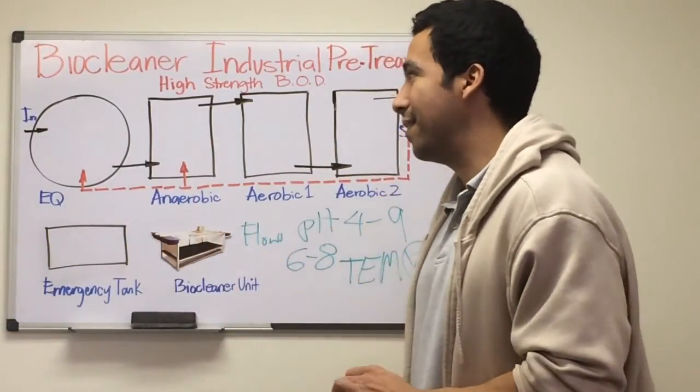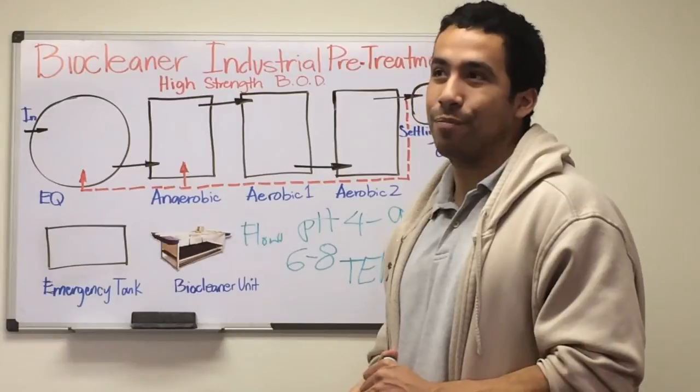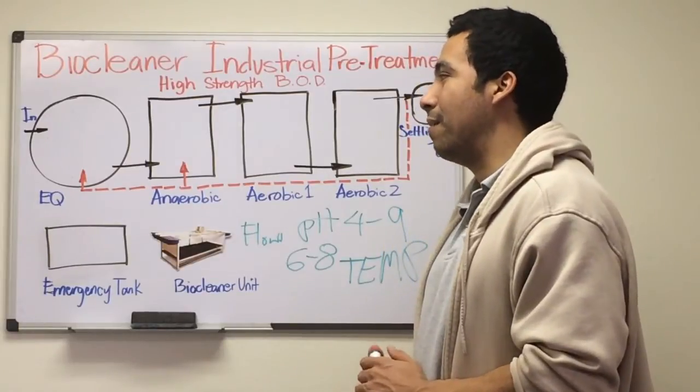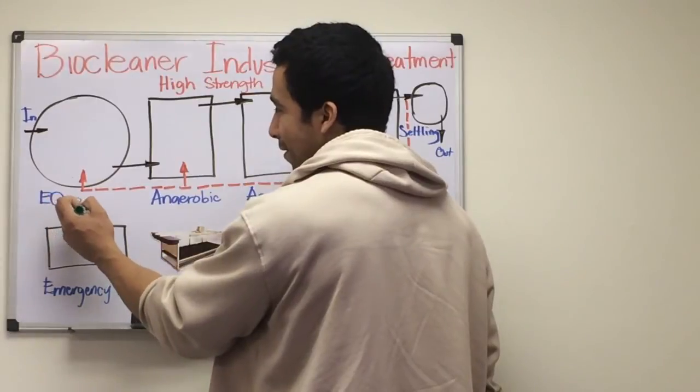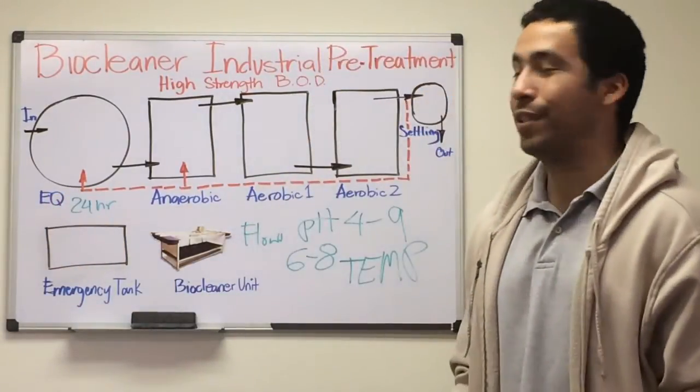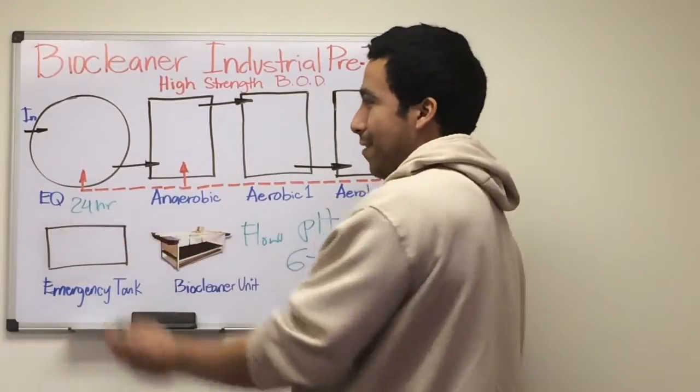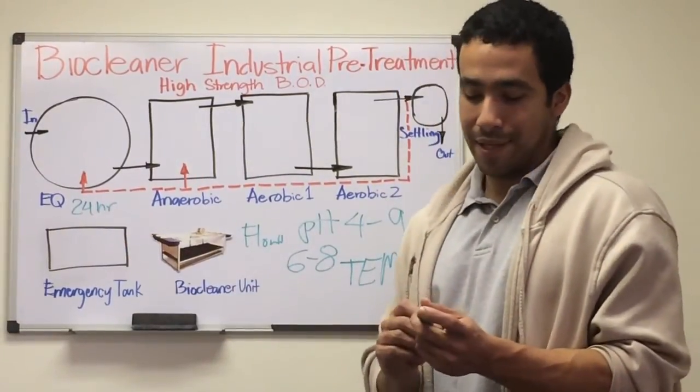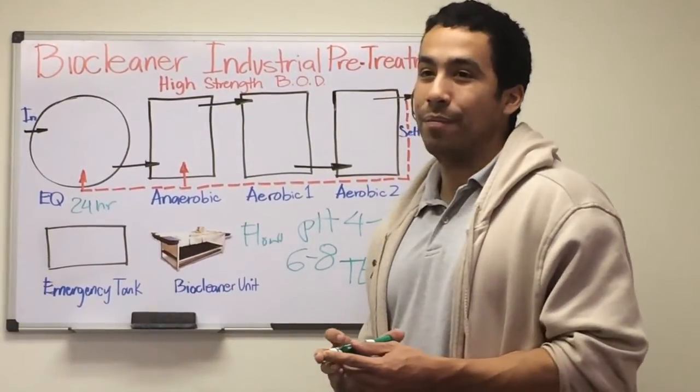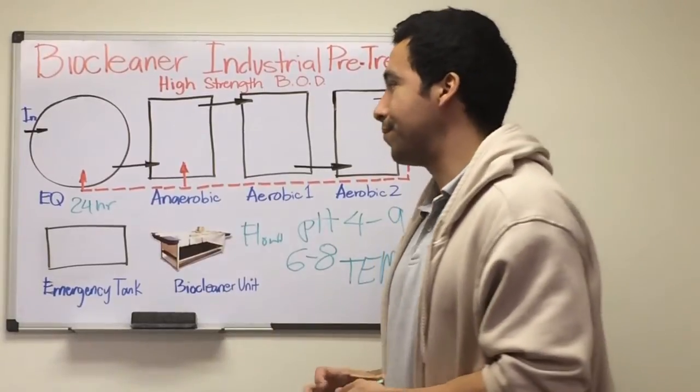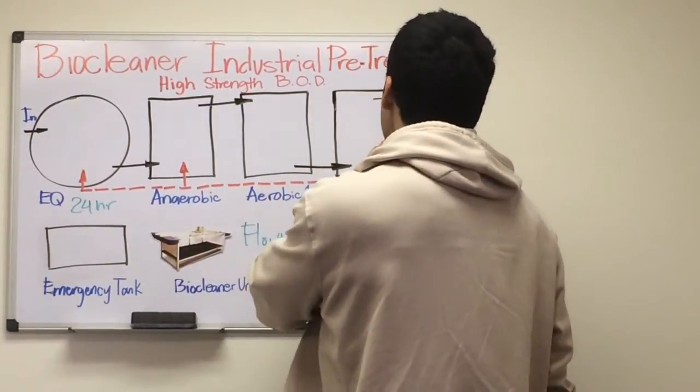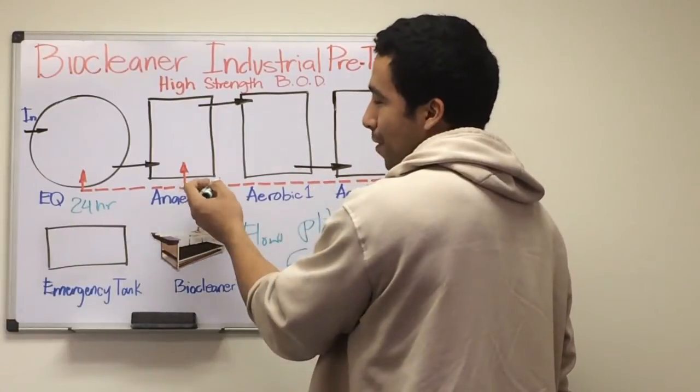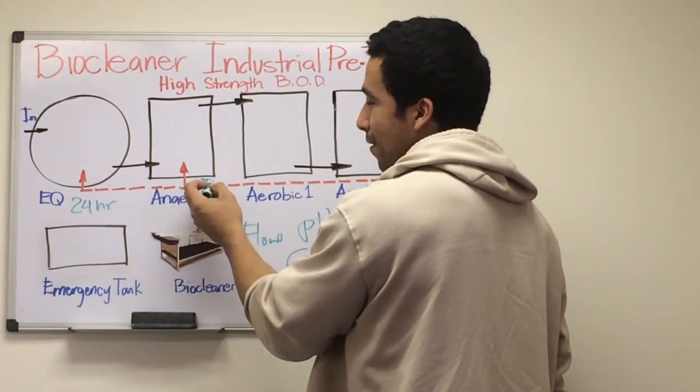To size an EQ tank depends on the industrial process and production schedule. Usually we consider a minimum of 24 hours of retention. However, if it's closed during the weekend, you may have to double it to 48 hours of retention time or even more depending on operation. Usually we do a return from 2% to 5% of the influent after the aerobic treatment.